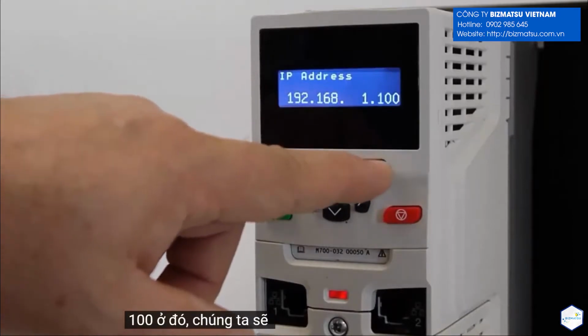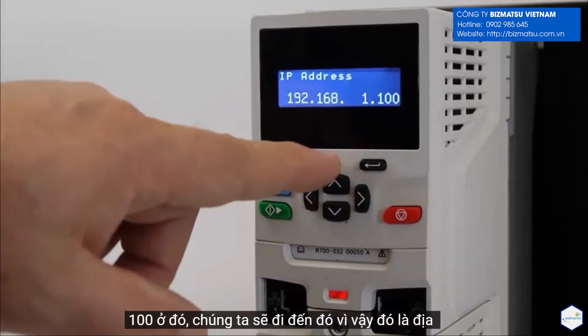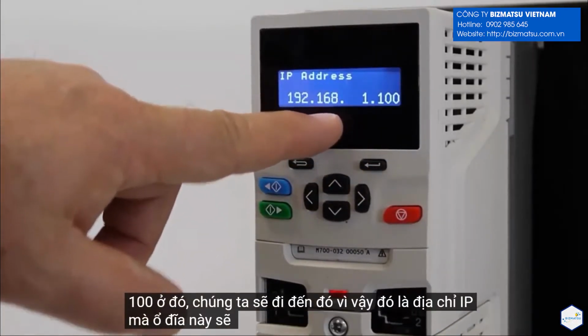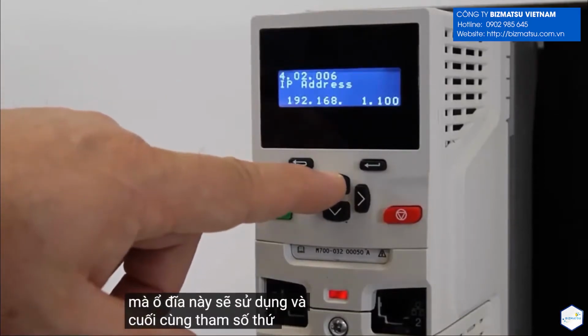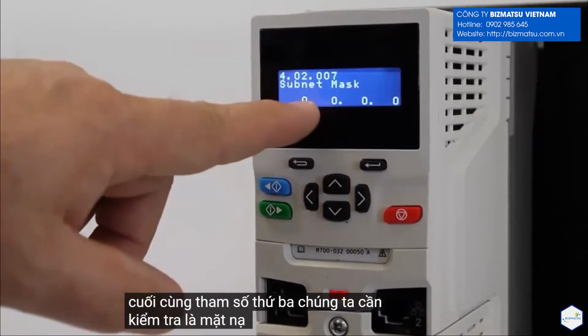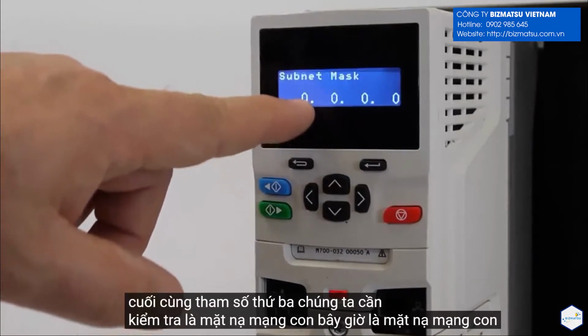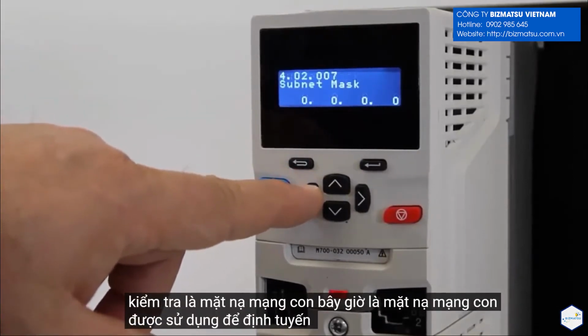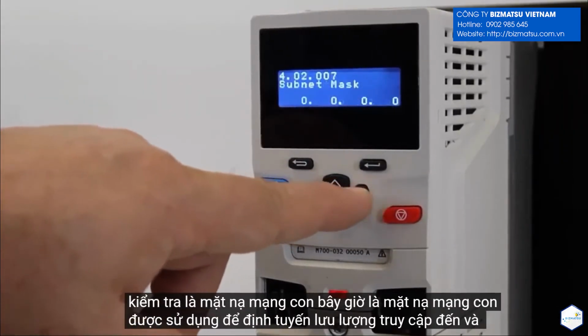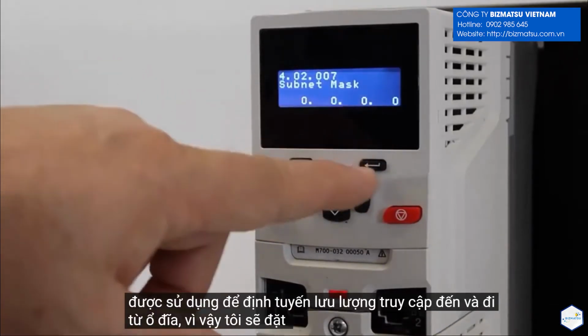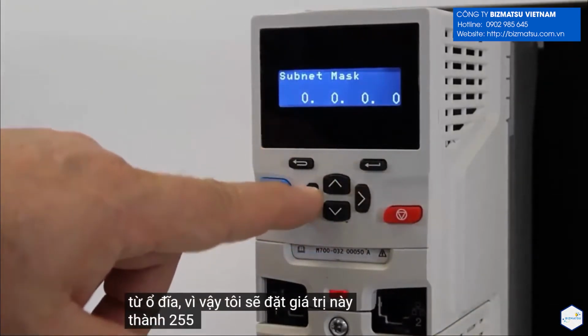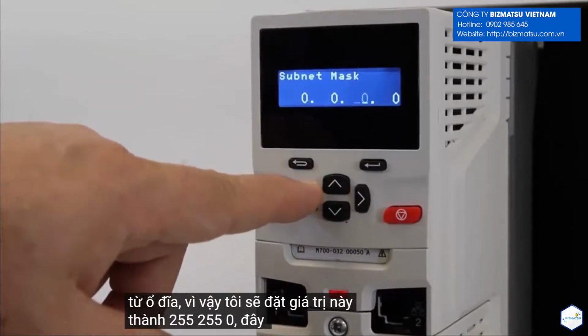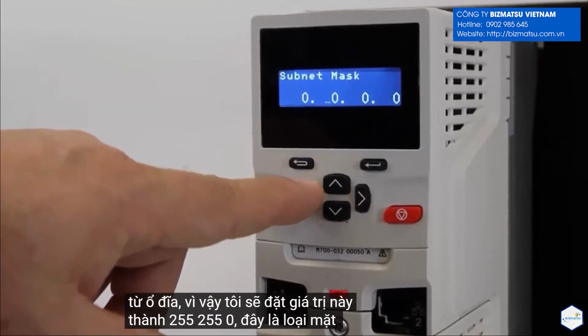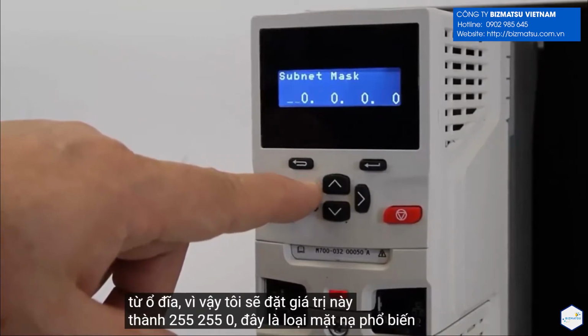100. There we go. So that's the IP address that this drive is going to be using. And finally, the third parameter we need to check is the subnet mask. Now, the subnet mask is used to route traffic to and from the drive. So I'm going to set this to 255.255.0, which is kind of a common mask.